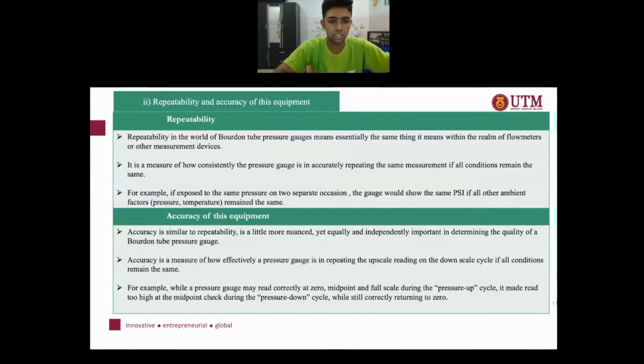And then the third question, they're asking about the repeatability and accuracy of this equipment. The first one, the repeatability in the world of Bourdon tube pressure gauge means essentially the same thing. It means within the realm of flow meters or other measurement devices. Second, it is a measure of how consistently the pressure gauge is accurately repeating the same measurement if all conditions remain the same. Last but not least, for example, if exposed to the same pressure on two separate occasions, the gauge will show the same PSI if all other ambient factors, which is the pressure and temperature, remain the same.